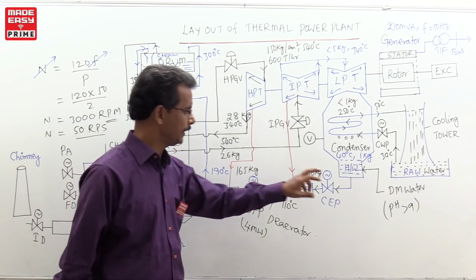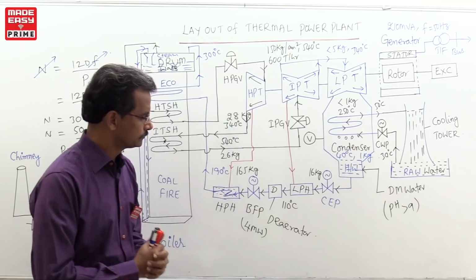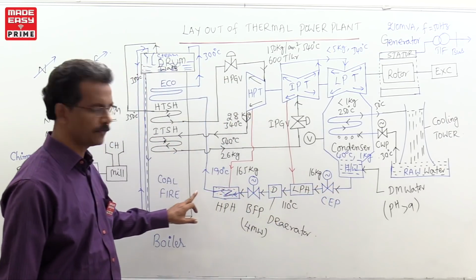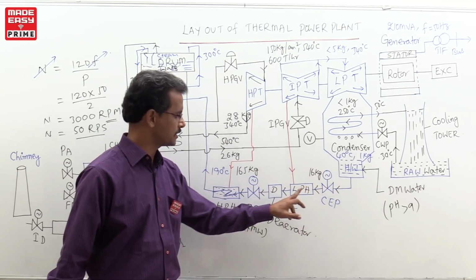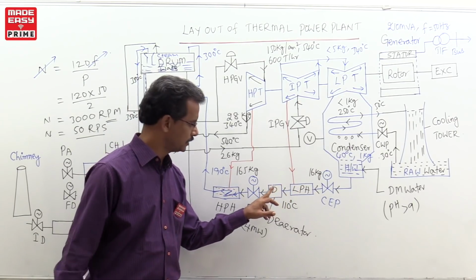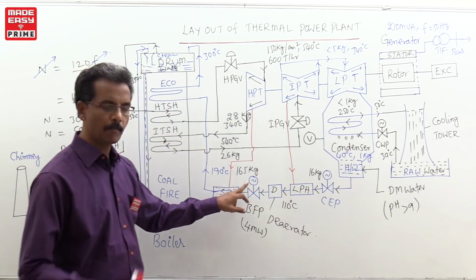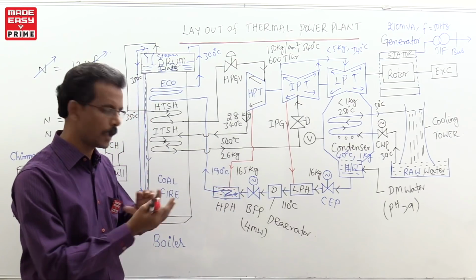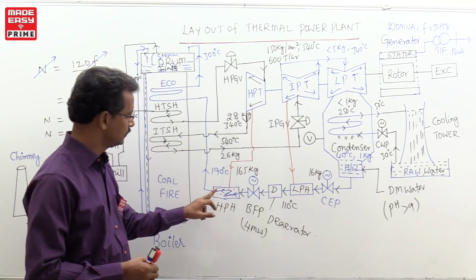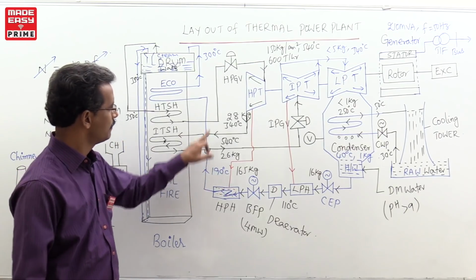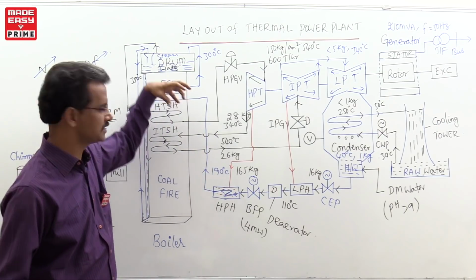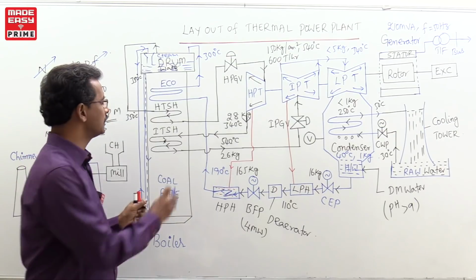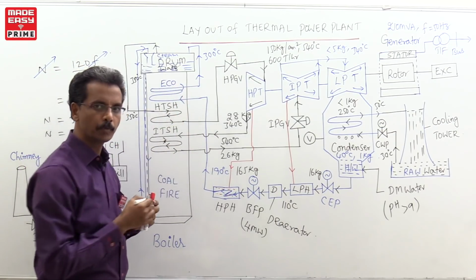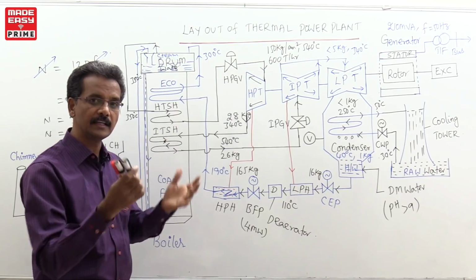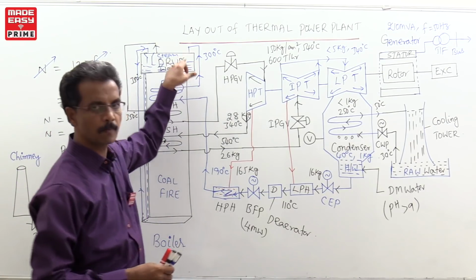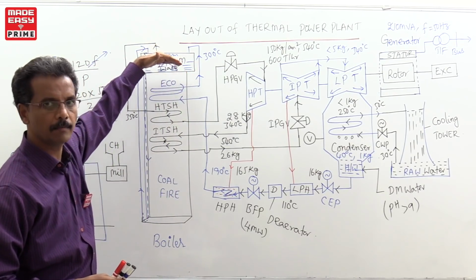Now, repeating, they are taking the water. Water is pumped, passing through different areas: the condensate extraction pump, the LP heaters, which raise the temperature, the deaerator, which removes the gas molecules, the boiler feed pump, which raises the water to high pressure, and the high pressure heater, which raises the temperature to 190 degrees centigrade, then passing through the economizer. It improves thermal efficiency by taking heat from the flue gases, so that the temperature of the water is improved without wasting the heat energy of the flue gases, and it passes to the drum, where the water comes inside the drum.